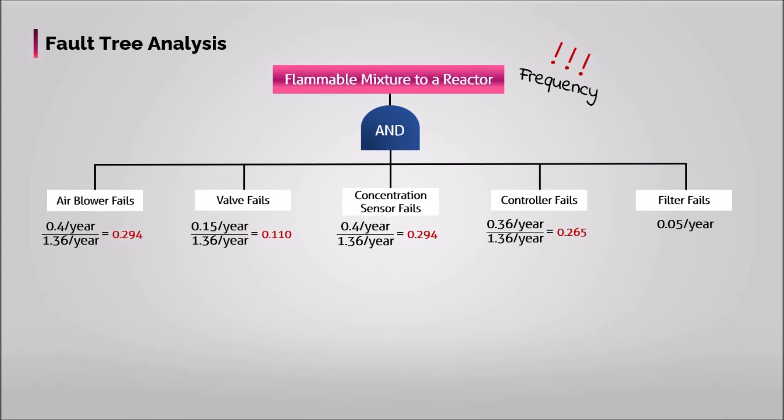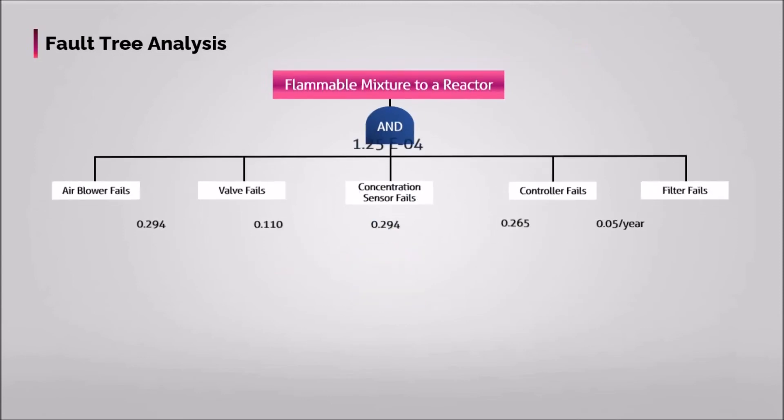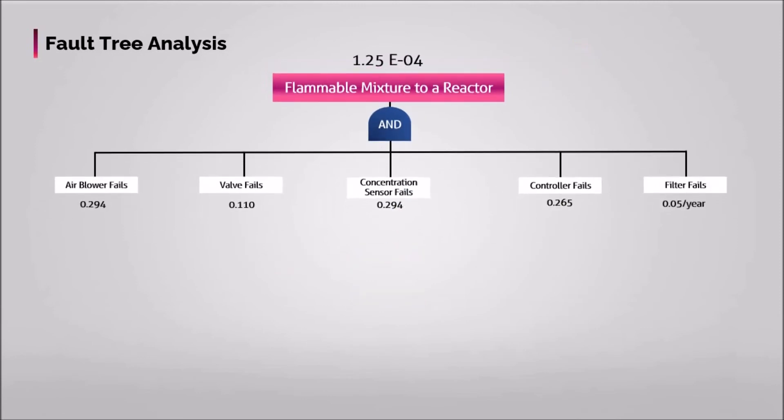Then, to calculate the frequency of flammable mixture to a reactor using AND gate, all likelihoods are multiplied. The results say, within here, the probability of flammable mixture to a reactor is 1.25 by 10 to power negative 4.